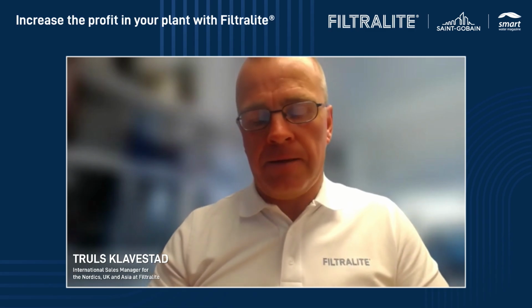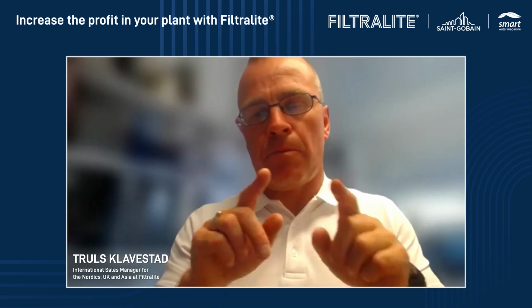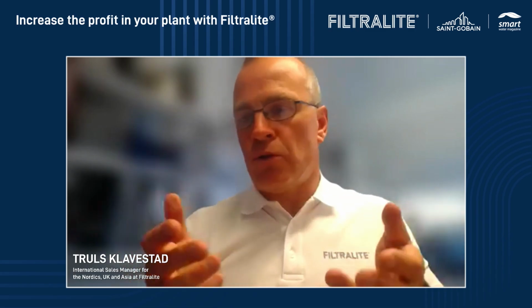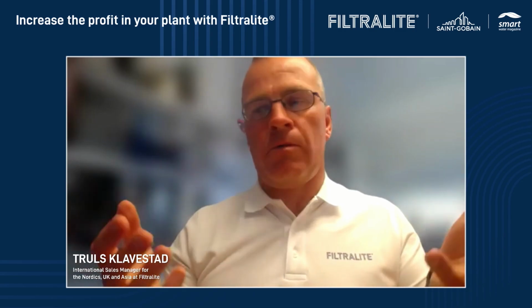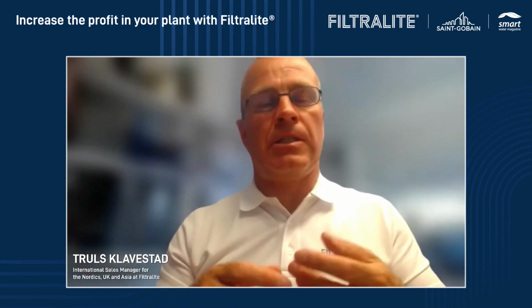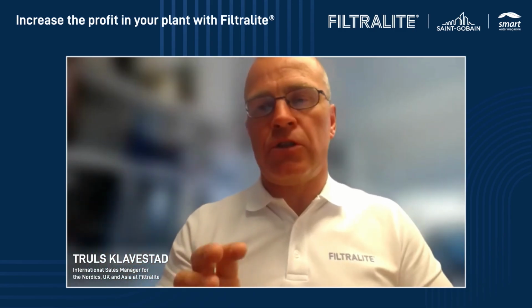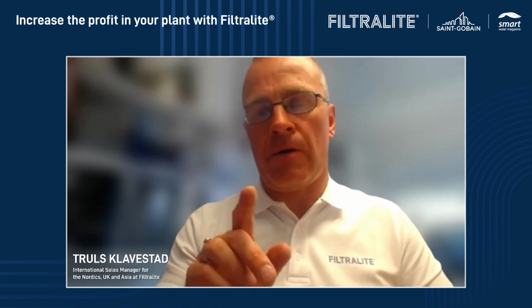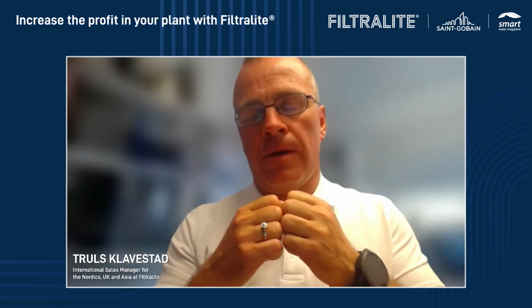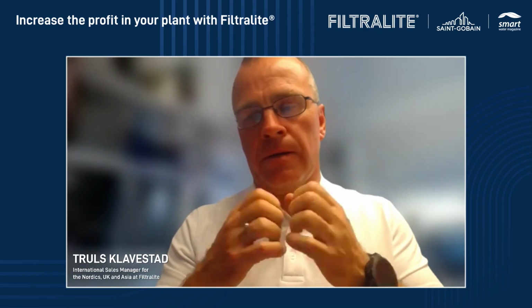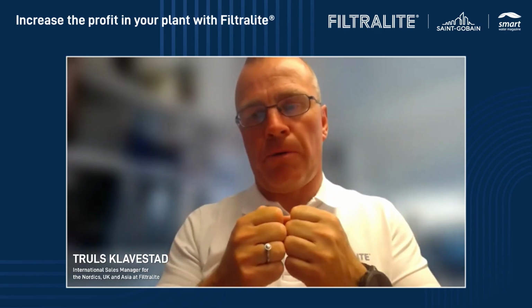And as I said, sand is the most used filter material in the world. Yes, it works, but it's very inefficient, and that is due to how the sand particles look. They are round. The only way you can trap the suspended solids is between two sand particles.